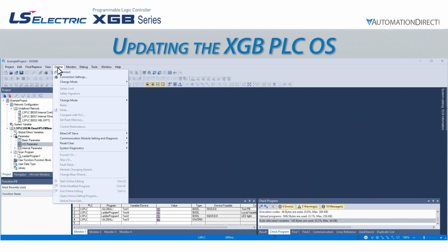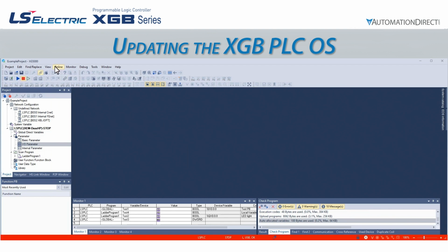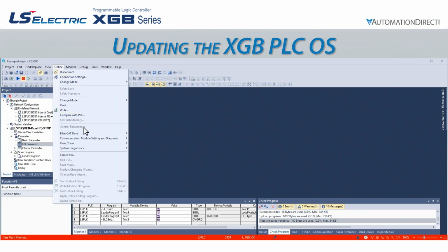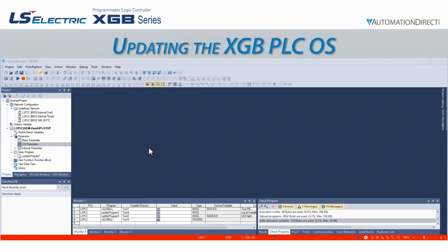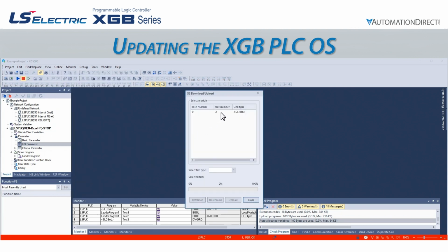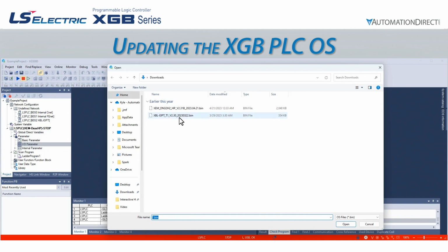In the software, we can go online with the CPU and go to Online menu, Communication Module Setting and Diagnosis, OS Upload/Download. It opens the pop-up window, OS Download/Upload, and we can see that our EIPT card is in slot 2. When we select that and choose the file type of OS, we can then click Download. This will open a new window asking us to select the binary file for the updated OS. We have this in our Downloads folder as well, and once we select it, we can click Open.